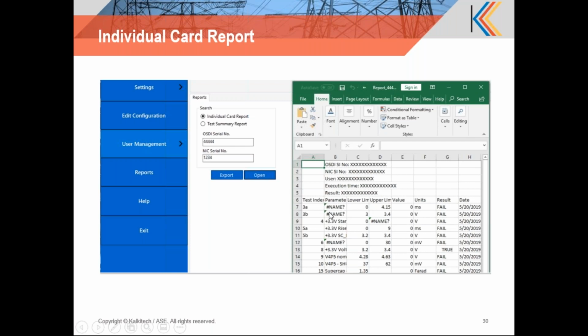You can see the individual test parameters being evaluated, the lower limit against the parameter, and the upper limit against the parameter. This lower limit and upper limit can be configured by the administrator. Then the value which is measured during the test, the unit, and the individual result. Since it's 0, it's a fail. The individual result of each test, and the date.